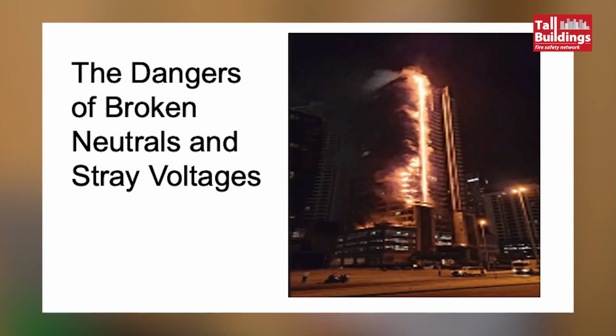There are two very dangerous sequences of events that happen. One is a broken neutral, which is when the neutral coming into the building, or on a submain within the building, either breaks or becomes loose. At that point, you've got a problem where voltages increase from 240 volts in buildings to 400 volts, leading to an increase in the speed of appliance motors, etc., and can lead to fires.